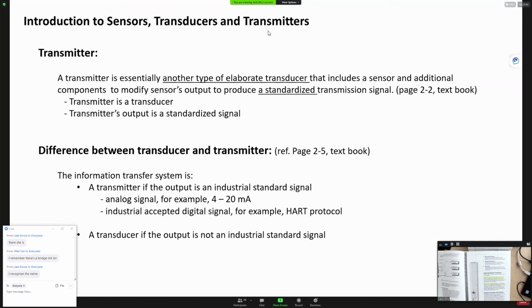Transmitter. Now we finally come to the last one. A transmitter is a type of transducer. The transducer will always have a sensor, but in this one we have an additional component to make sure the output is a standardized signal. That's in your book 2, page 2. A transmitter is a transducer. The transmitter's output is a standard signal.